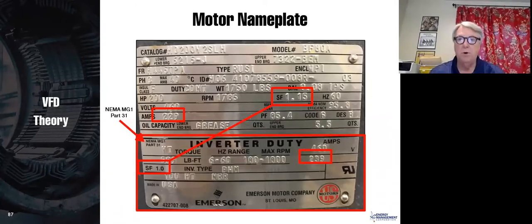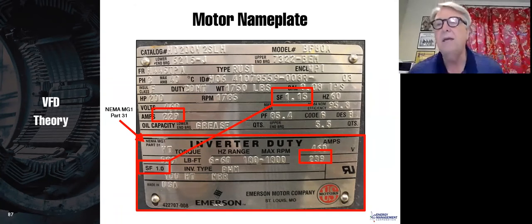Now, here is a motor nameplate. I've showed you this before if you were in our motor section. Notice that when you run a VFD, you always want to run a service factor motor. But when you run it on a VFD, you can't use the service factor. And the reason for that, as we looked at in our motor class, is that when the motor slows down, the fan on the motor shaft slows down, and the motor doesn't get as much cooling. Therefore, you use up your service factor in allowing the motor to run slower.